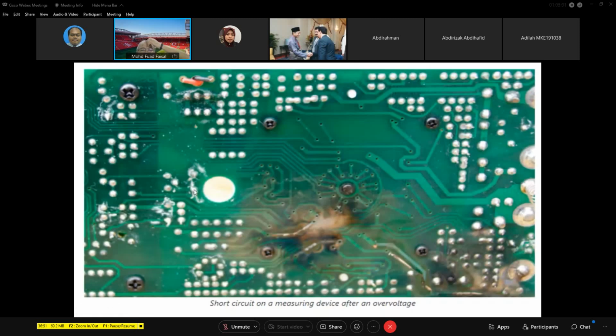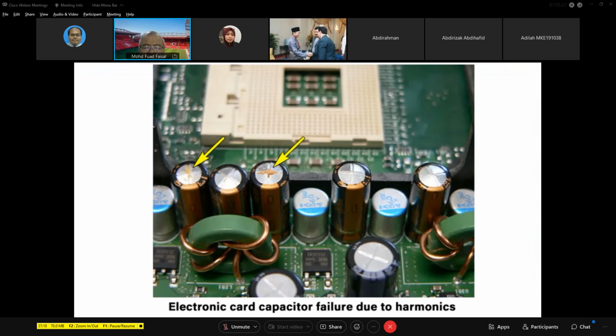Okay, this is also another news clipping. I put up the photo. So customers are complaining about their circuit boards, their wiring circuitry being damaged by overvoltage. So this is basically due to lightning strikes. So lightning strikes can damage sensitive equipment. Okay, this is another report about electronic capacitor failure. So this is a very, very real issue in Malaysia in particular, because we have lightning, and then we have semiconductor industries, and later on I will share about the impact of electronic gadgets that cause harmonics. So sensitive equipment is very sensitive or prone to harmonics.